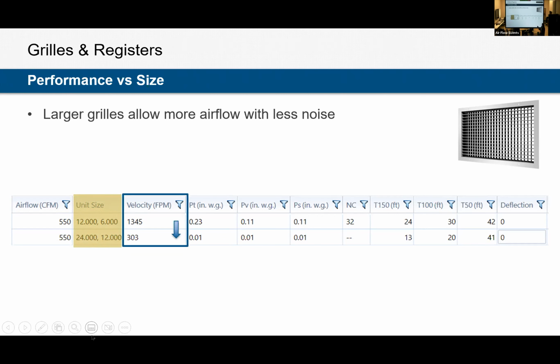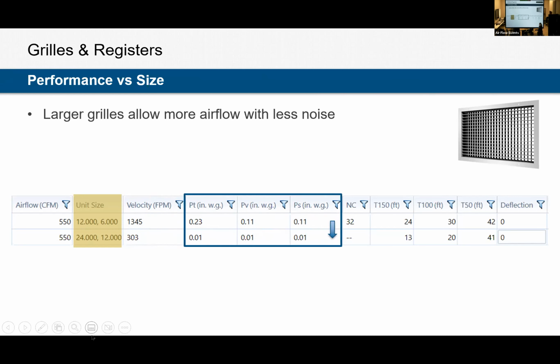It's not exactly double. Quadruple. Yes, yeah, because it's a square dimension. You're doubling each length. Thank you. Our velocity is going to decrease substantially. You're moving the same amount of airflow through a larger opening, so our air will move slower. We're also seeing a reduction in pressures across the board. Your total pressure, velocity, and static pressure are all reduced because we have less resistance to the airflow.